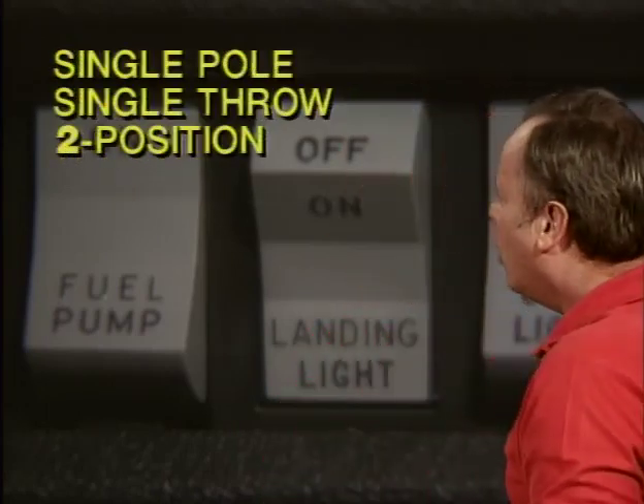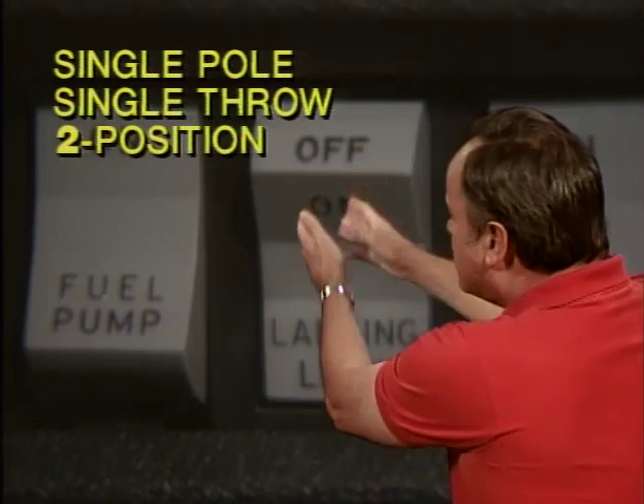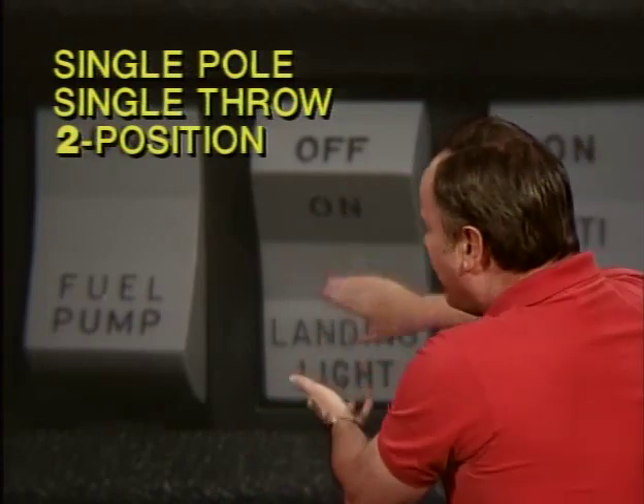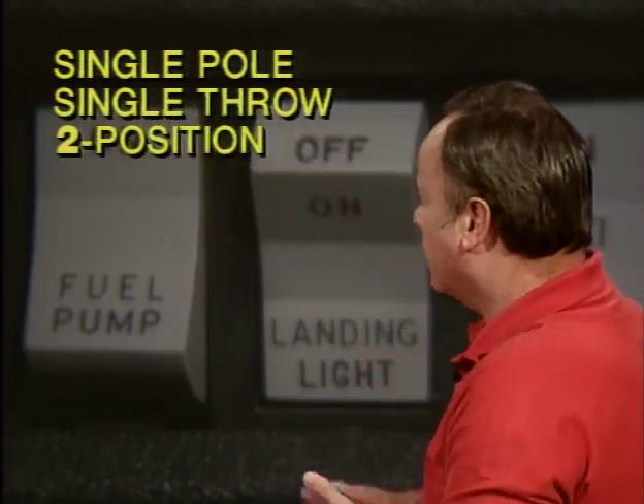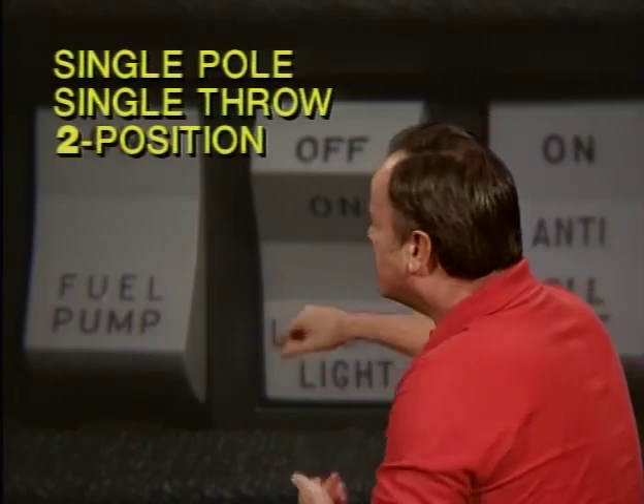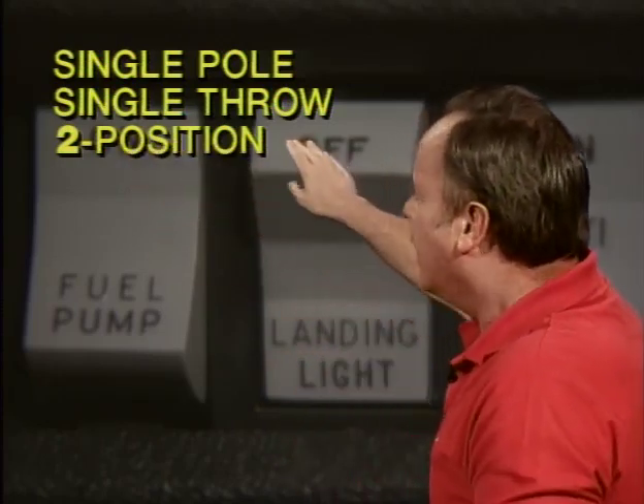Well, you're only activating one circuit per lever, so it's a single pole switch, and it can only go in one direction, so it's a single throw switch. It's also called a two-position switch. What are those two positions? On and off. That's why it's called a two-position switch.